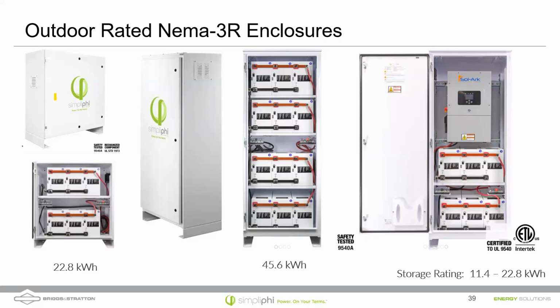But with the AmpliPHI and the SimpliPhi batteries, the ones that have the closed loop communications, we're letting you charge those at a much colder temperature, down to -20 degrees centigrade, up to 70 degrees centigrade. Why is it that the communicating batteries can be charged at a colder temperature? Well, that's a great question, Daniel.